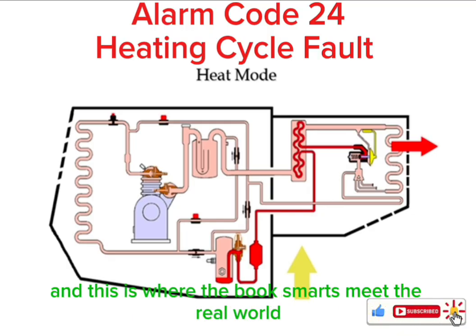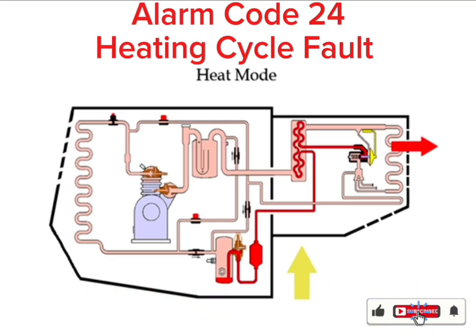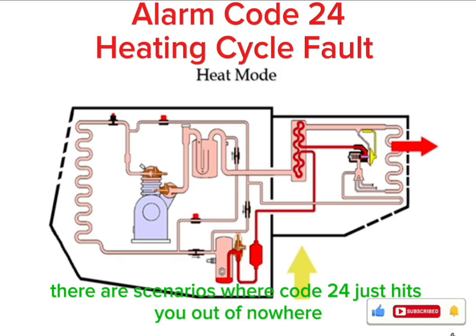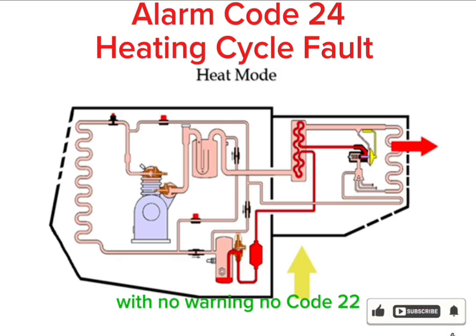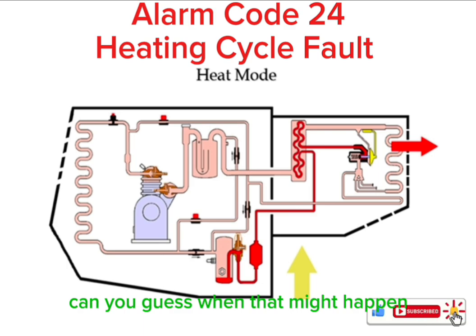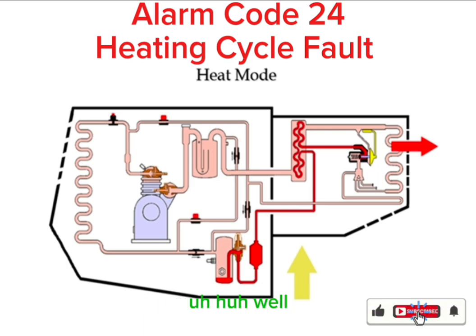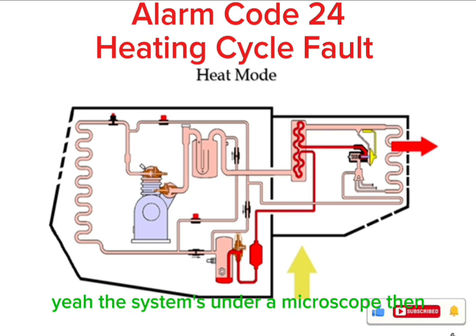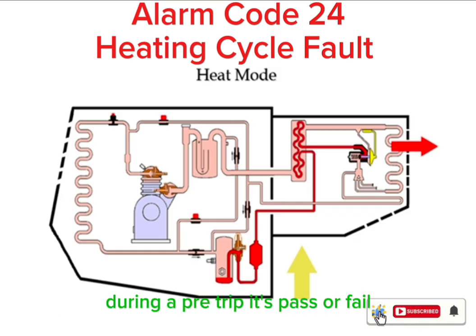But, and this is where the book smarts meet the real world, there are scenarios where code 24 just hits you out of nowhere. With no warning. No code 22. Just straight to shut down. Can you guess when that might happen? Well, I'd guess during a pre-trip test. Yeah. The system's under a microscope then. That's one. During a pre-trip, it's pass or fail. There's no check me later. If the heating cycle fails that test, it throws code 24 immediately.